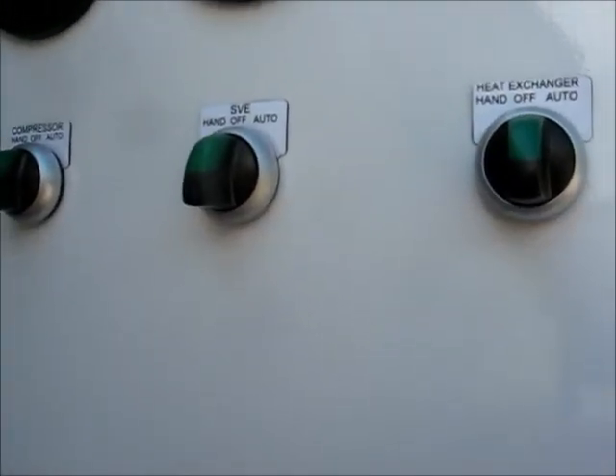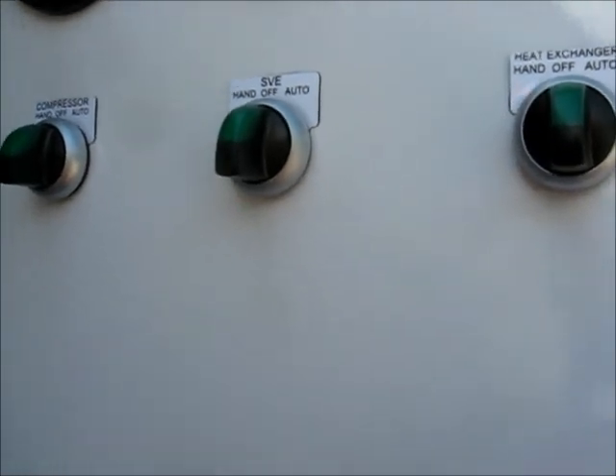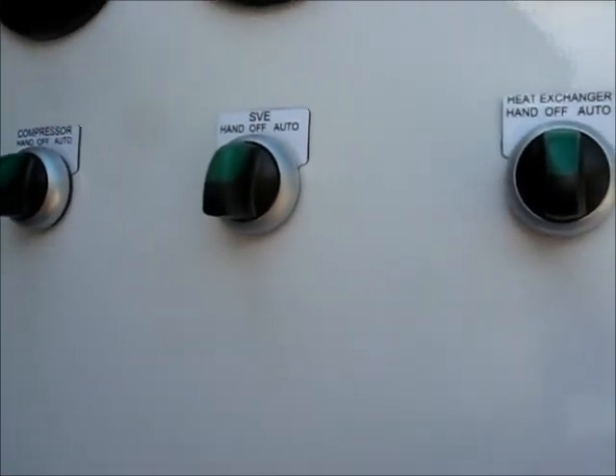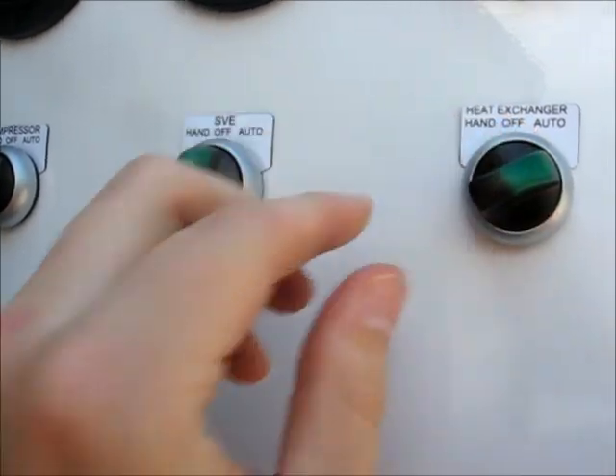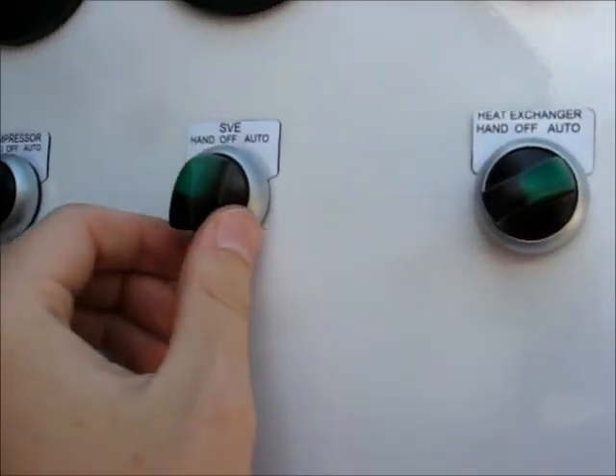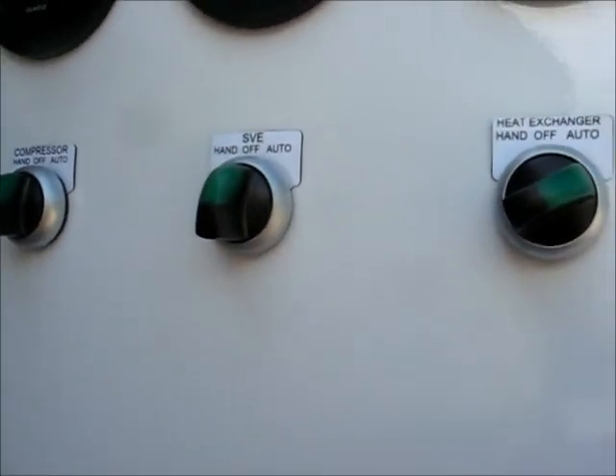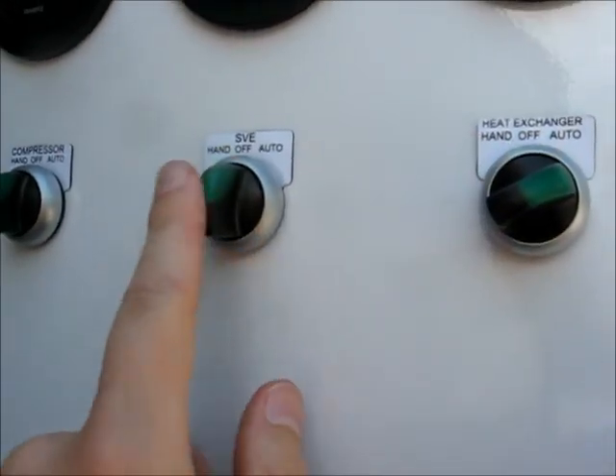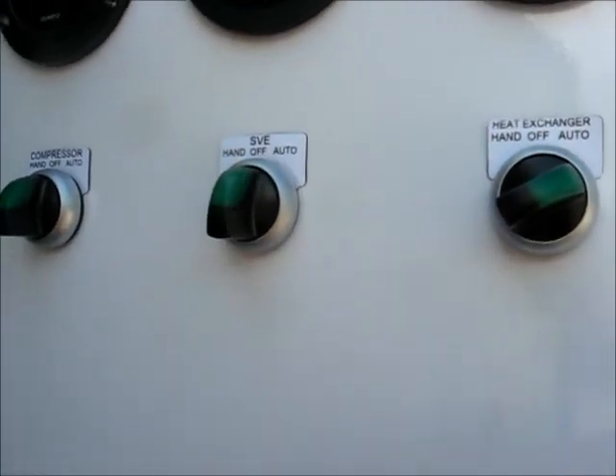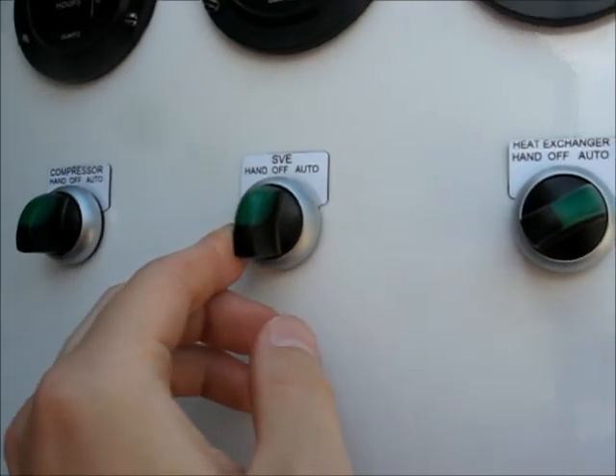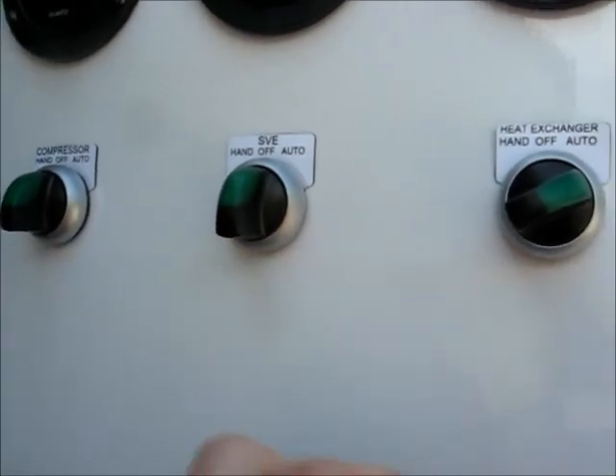So if we turn all these switches on, it should take a couple of seconds for the air compressor to come on. So we'll turn the heat exchanger on. You can see the SVE doesn't come on, or the heat exchanger does not come on unless the SVE is on. So that's our interlock for the air sparge and the SVE. It kind of has a cascading effect.